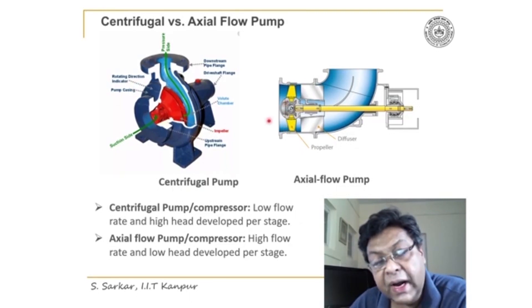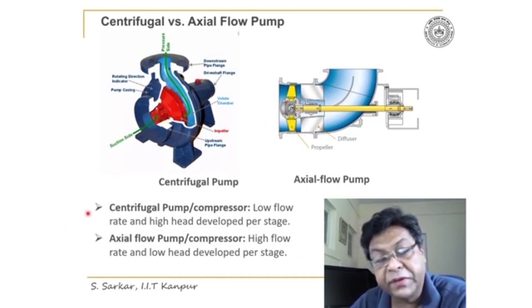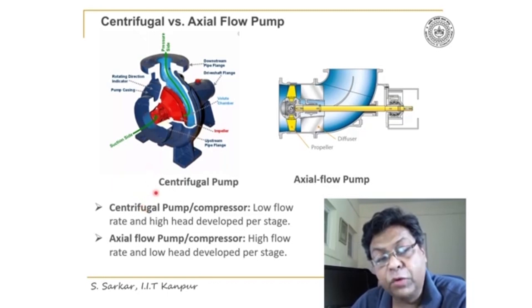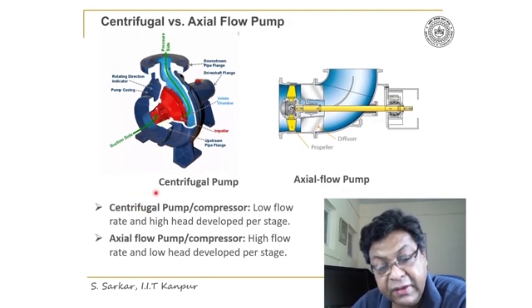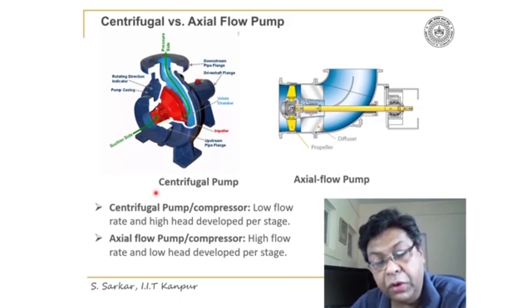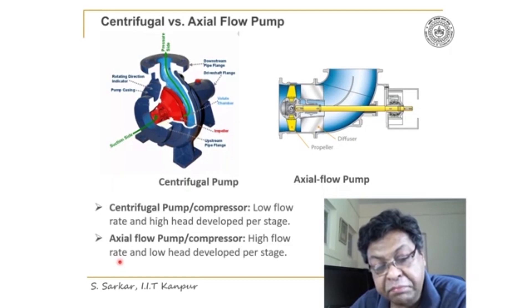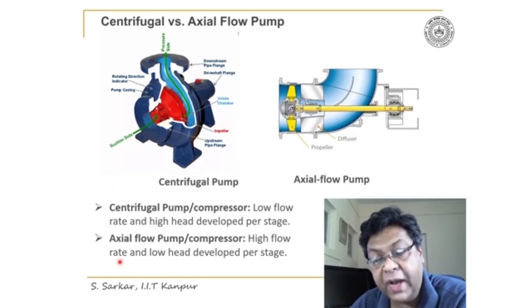In summary, in a centrifugal flow pump the pressure rise per stage is high while the volume flow rate tends to be low. On the contrary, in an axial flow pump the pressure rise per stage is low and the volume flow rate tends to be high.